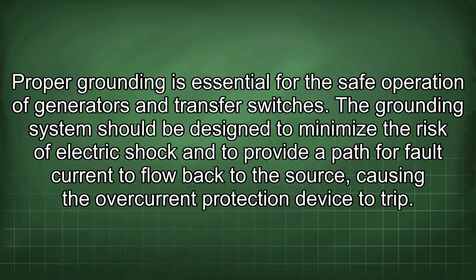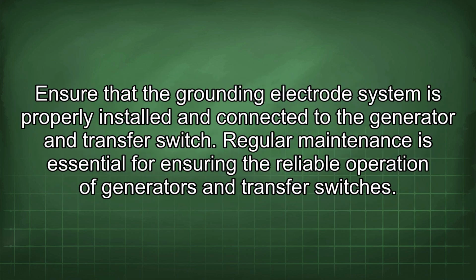The grounding system should be designed to minimize the risk of electric shock and to provide a path for fault current to flow back to the source, causing the overcurrent protection device to trip. Ensure that the grounding electrode system is properly installed and connected to the generator and transfer switch.